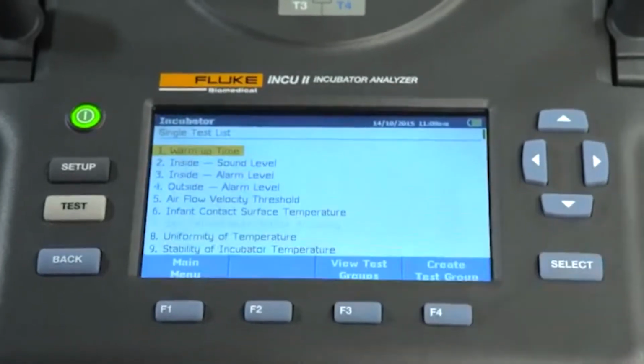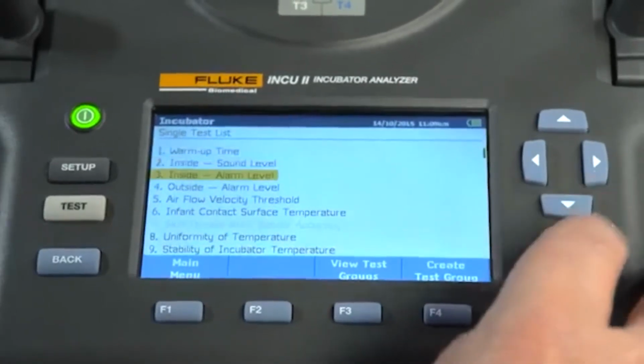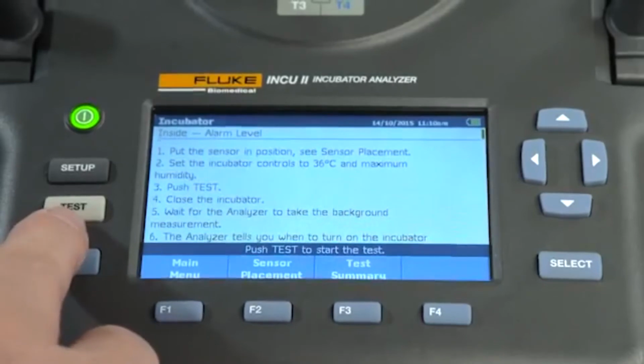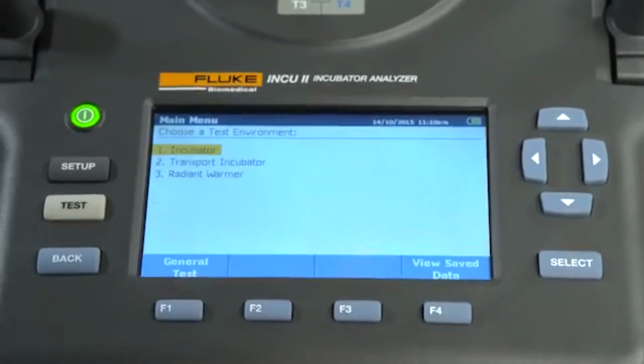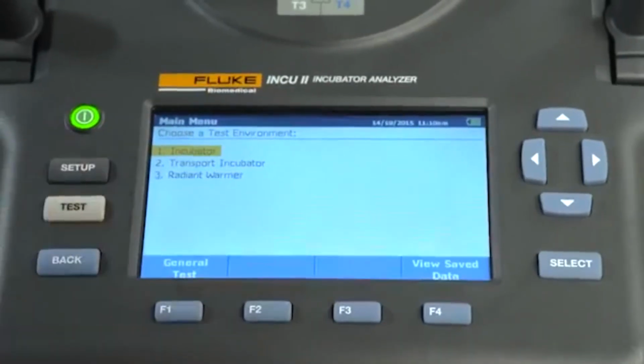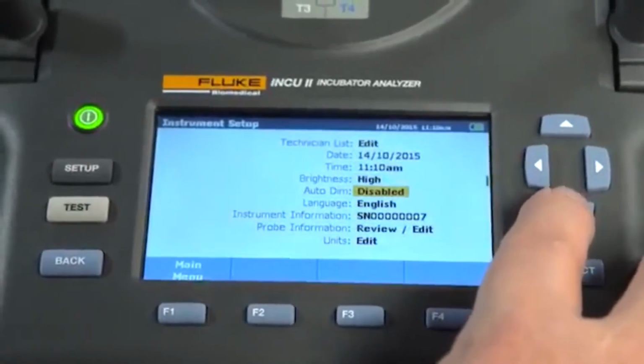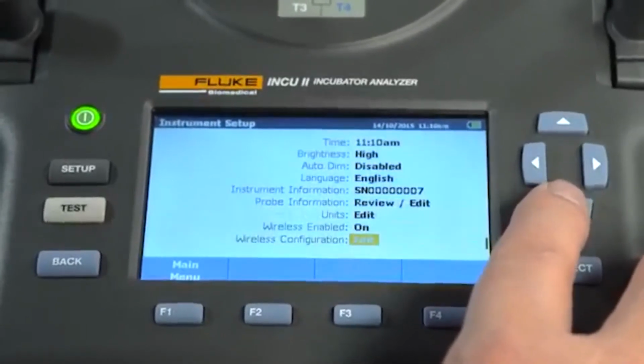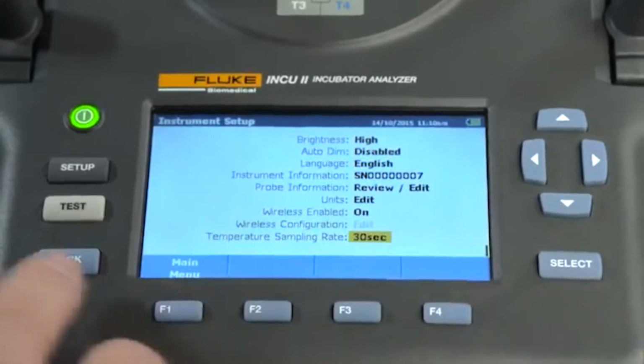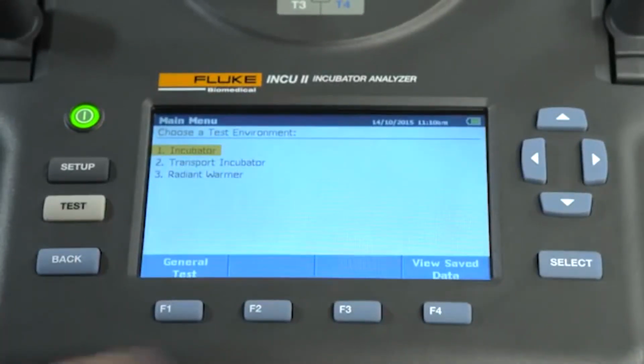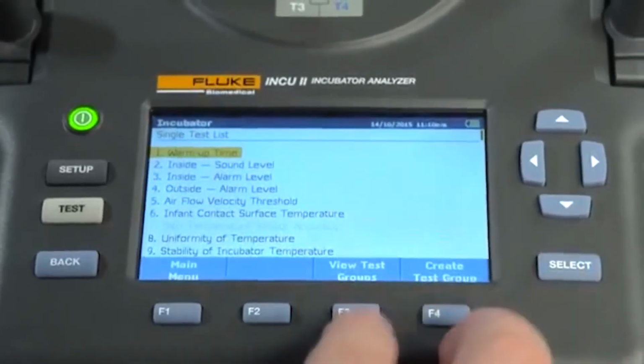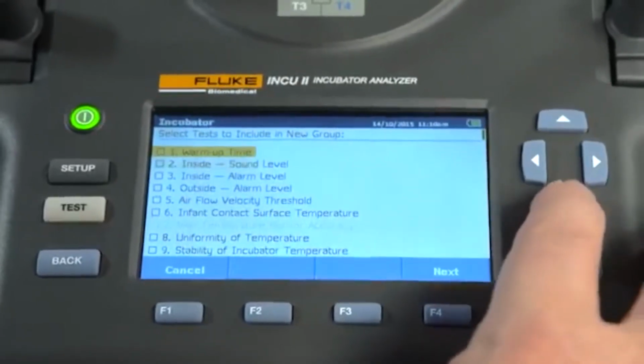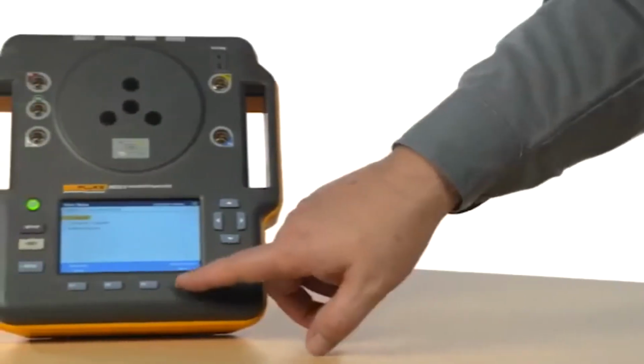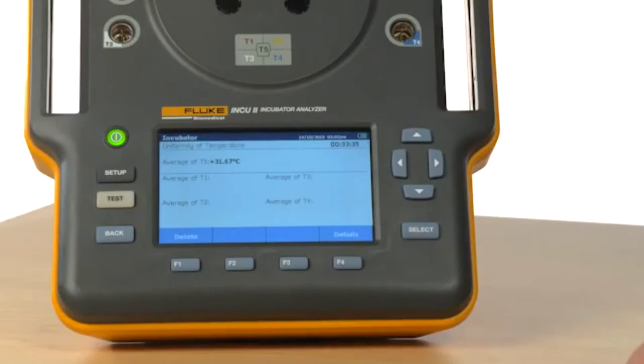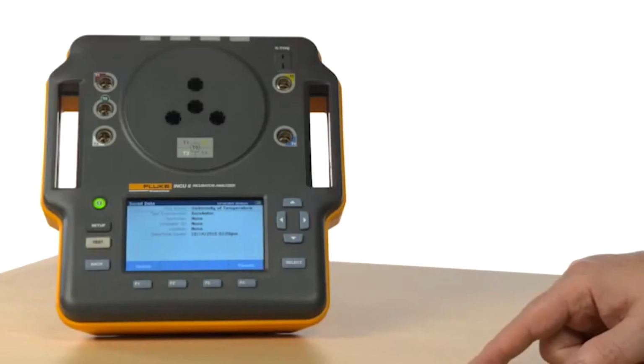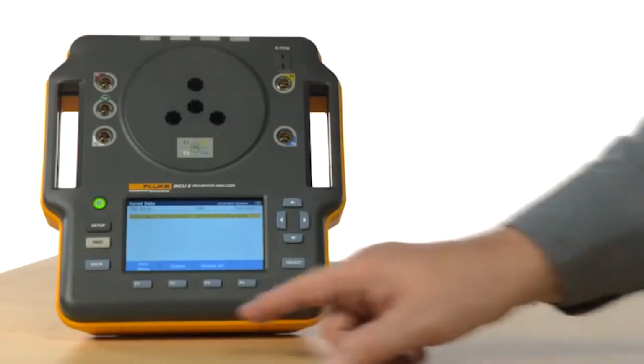Let's choose the IEC standard we want to test against. Follow the on-screen directions, then press Test. The INCU2 displays test results in real time. At the end of a test, either pass or fail indicators will be displayed. The Setup button allows you to change your measurement units, view the details of the device, and select your sampling rate. The Back button allows you to go back to the previous screen. Along with using the standard tests, you can create your own testing groups or unique testing procedures, which can further increase efficiency and tailor testing to your facility's protocols. After running a test, be sure to save the results. The results will be saved to the device and its onboard memory. It can then be uploaded to your computer wirelessly or by using a USB cable. Ask your sales representative for more information about wireless capability in your country.